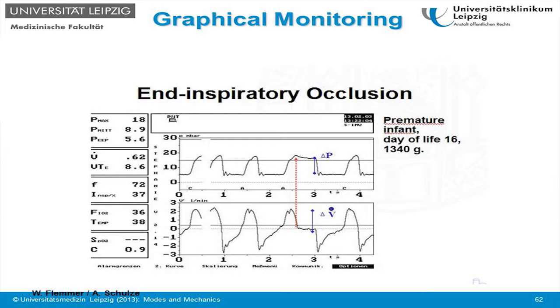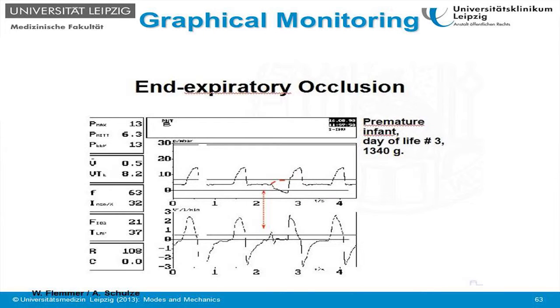Some machines also can do occlusions to measure static compliance values. This is an inspiratory occlusion. The machine closes the airway opening and then measures the pressure that builds up, and we see that the pressure is here, and with this pressure measurement you can determine the static compliance of the patient, which is more accurate than the dynamic compliance of the patient. With an expiratory occlusion, what we see here, we see a pressure drop after the occlusion, which means that the patient probably had gas trapping and you need to prolong the expiratory time.